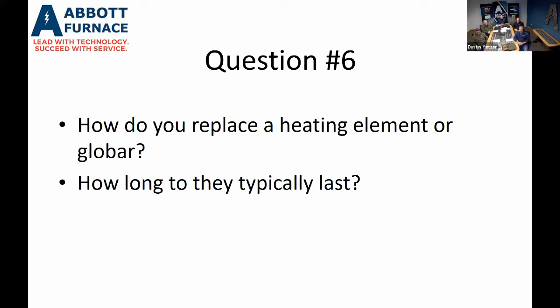Again, how long do they typically last? The biggest issue with globars is a lot of people take their high heats up and down in temperature. That temperature variation really wreaks havoc on globars. What makes a globar wear out faster is the higher percent output that you run on them. If you run them at full blast all the time, your globars usually don't last very long.